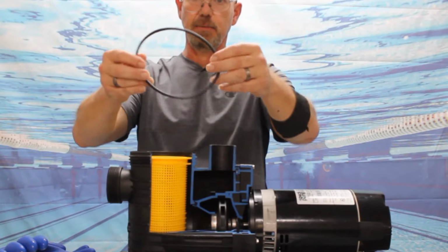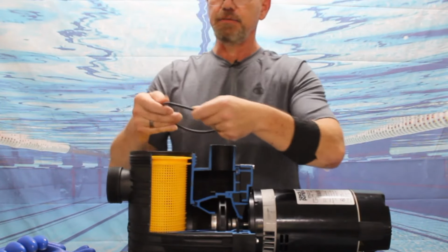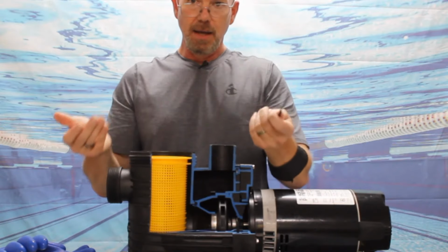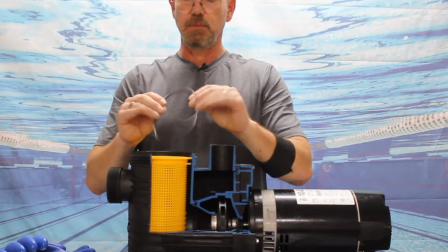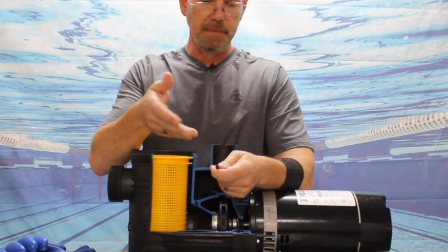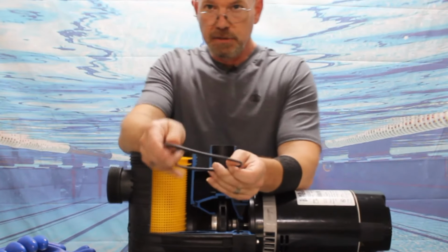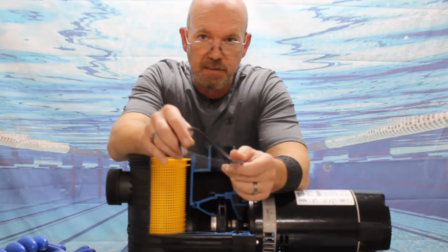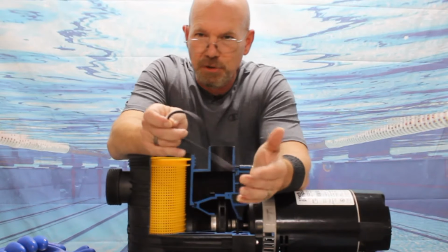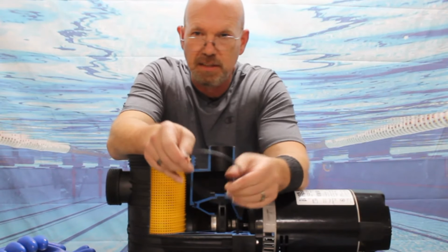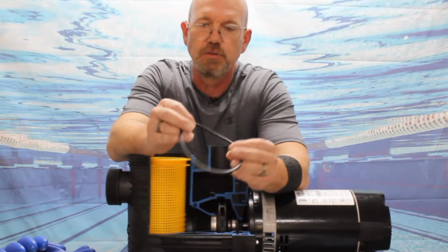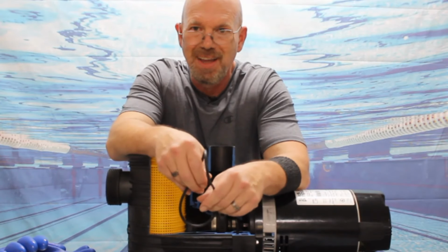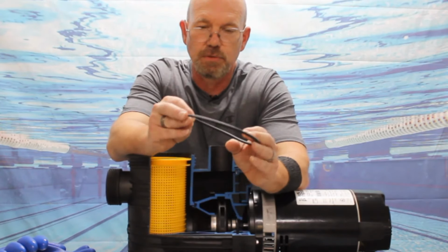If that's the case, then we want to replace the O-ring. If it looks in good shape, we'll just make sure that it's been lubricated. We want to lubricate these things every time that lid comes off. To do that, we want to use a silicone or Teflon-based lubricant. We don't want to ever use a petroleum product like Vaseline or anything along those lines. Petroleum products do degrade rubber, so you'll go through more O-rings and gaskets over time.